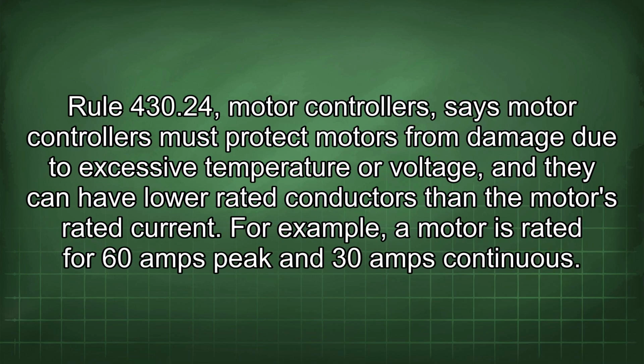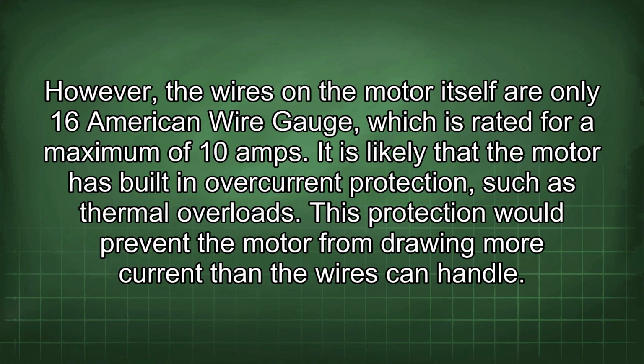Rule 430.24, Motor controllers, says motor controllers must protect motors from damage due to excessive temperature or voltage, and they can have lower rated conductors than the motor's rated current. For example, a motor is rated for 60 amps peak and 30 amps continuous. However, the wires on the motor itself are only 16 American wire gauge, which is rated for a maximum of 10 amps. It is likely that the motor has built-in overcurrent protection, such as thermal overloads. This protection would prevent the motor from drawing more current than the wires can handle.